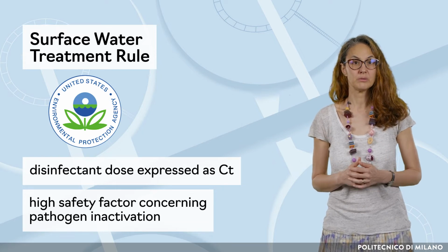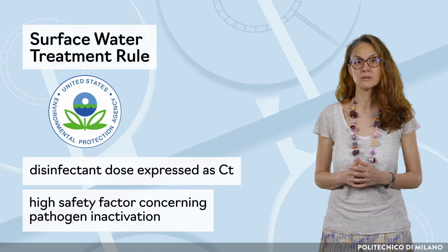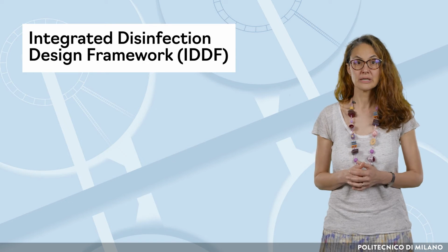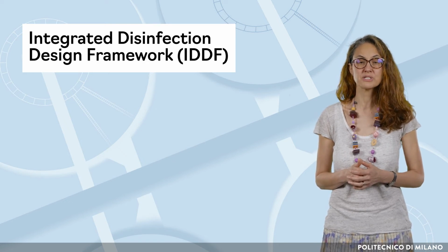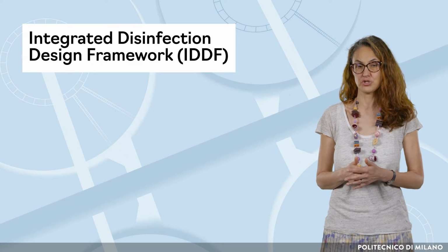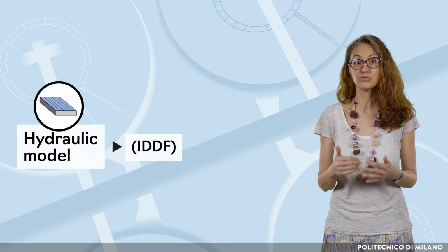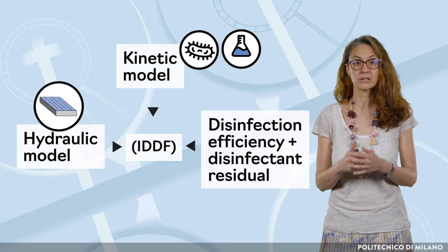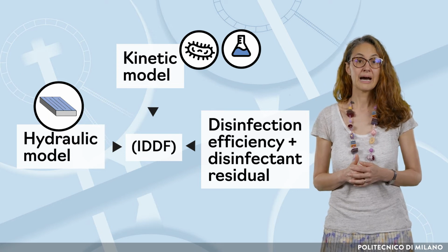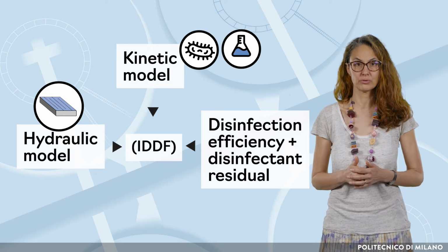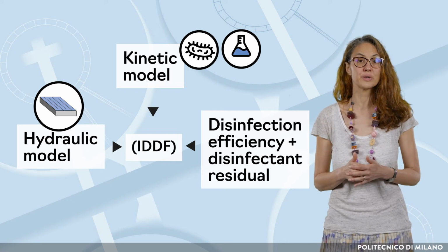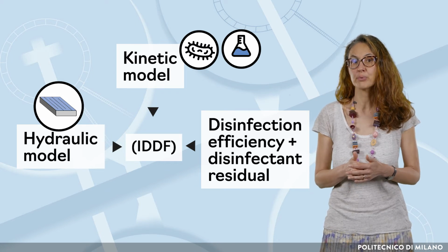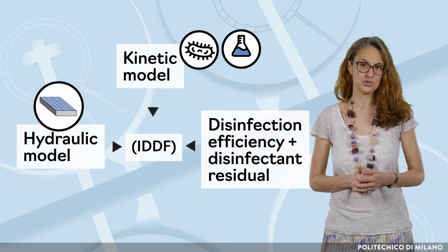The step forward in modeling the disinfection process is represented by the Integrated Disinfection Design Framework, IDDF, which led to a fundamental shift towards a site-specific modeling of continuous flow disinfection, which considered contact tank hydraulics, microbial inactivation kinetics, and disinfectant decay and byproduct formation. However, IDDF was developed for drinking water and considers disinfection as a stationary process with constant water quality and flow rate, which makes it very approximate for realistic wastewater applications.